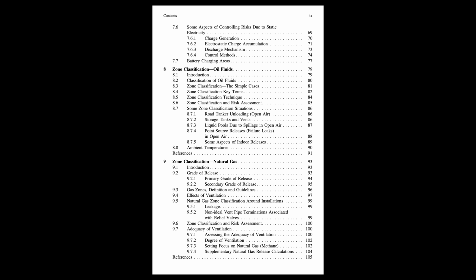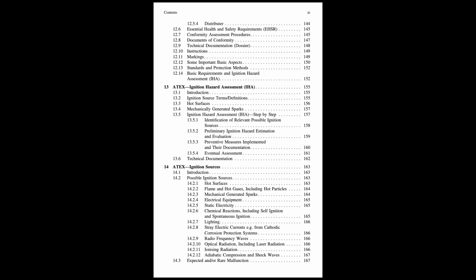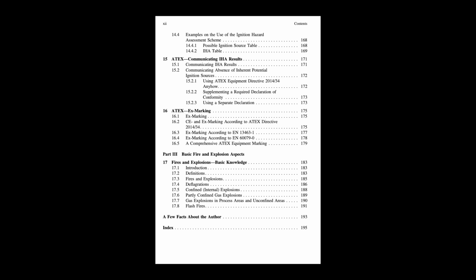That's a huge range of sources. So how do we control the risks from static? What are the main strategies? The number one strategy is preventing charge accumulation by providing a path for static charges to safely dissipate or recombine before they reach dangerous levels. Earthing, basically. Earthing or grounding is absolutely fundamental. All conductive components, metal pipework, vessels, equipment housings, structural steel, even mobile equipment like trolleys or drums must be bonded together and connected to earth with a low resistance path.